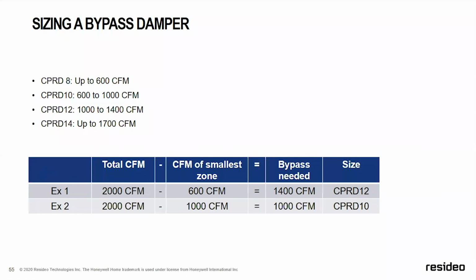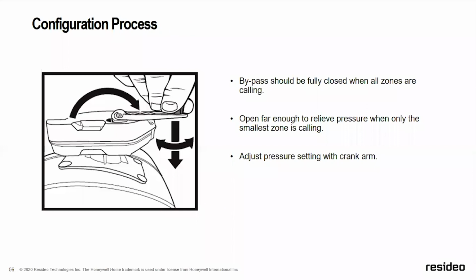Now, typically, if my smallest zone is 600, you can see by the math on the bottom, if I have a 5-ton system, 2,000 CFM, smallest zone 600, the bypass needed would be 1,400. Now, the caveat to that is you can also use bleed rate in your configuration. So if I have bleed rate on 2 zones and my smallest zone is 600, I'm able to get away with maybe a CPRD 10. So there are ways to get around if you don't have room to do a CPRD 12, but you know you need one. If you do bleed rate, you can go down to a 10. To adjust the CPRD, you simply pop open the crank and adjust it as needed.